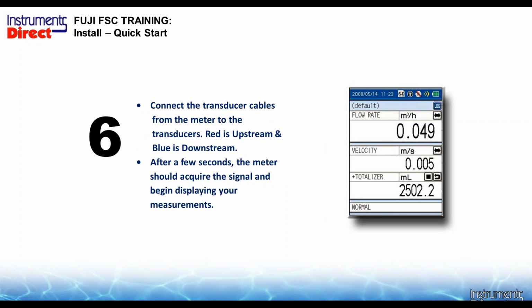So we go and connect the cables to the transducer. The red is the upstream, the blue is the downstream. What if you flip them the wrong way? Well, instead of getting a positive reading, you'll get a negative reading, but everything is hokey dokey as far as flow rate, just subtract or add that positive or negative, and away you go. So it only takes a few seconds to actually get your meter to read.